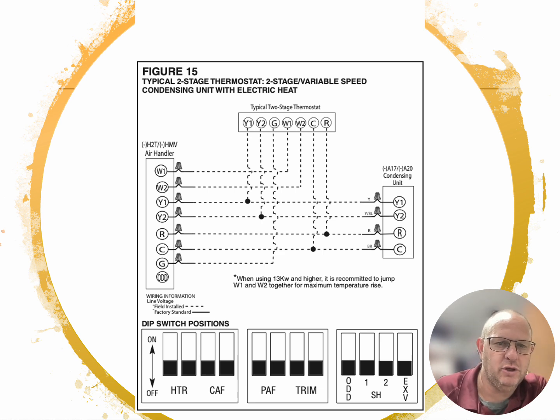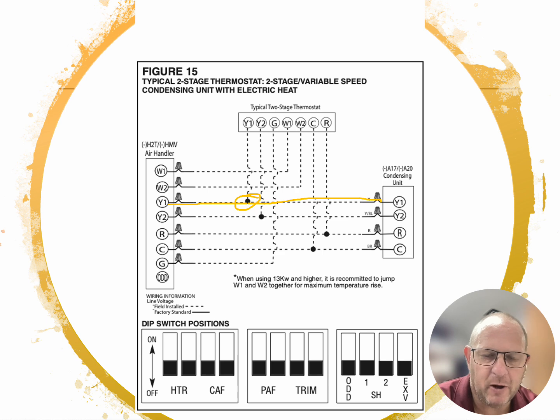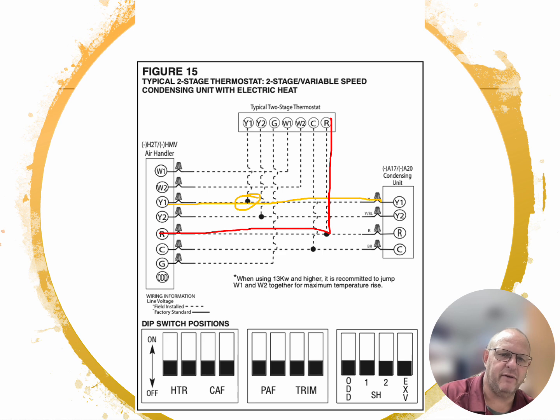So first stage is going to be Y1. That's going to be your cooling. Notice that these are connections right here, and they're basically taking this wire out to the outdoor unit. Make all of your connections on the indoor unit. So the R is coming up to the thermostat. Sequence of operation tells us that the thermostat is just a switching device. Okay, coming up there. We also have a wire running out to the condensing unit. This one must have a board that needs to be powered. So that's why the R is going out there.